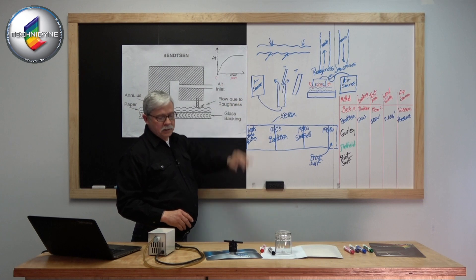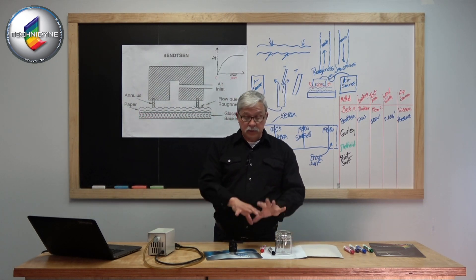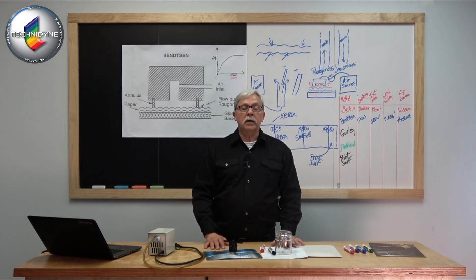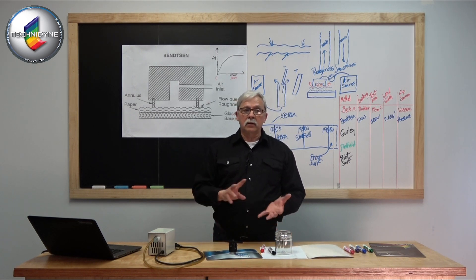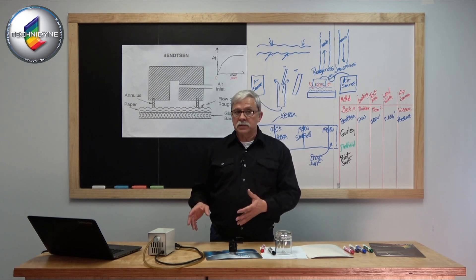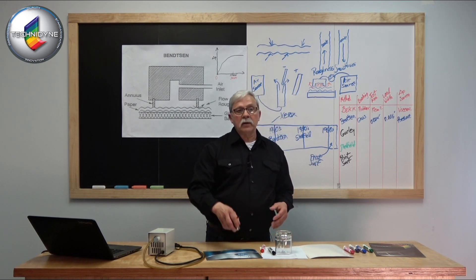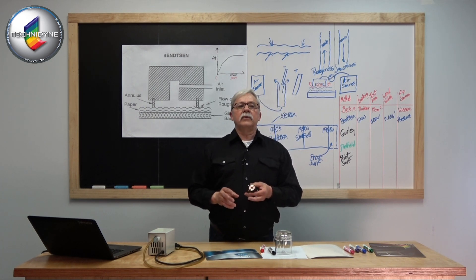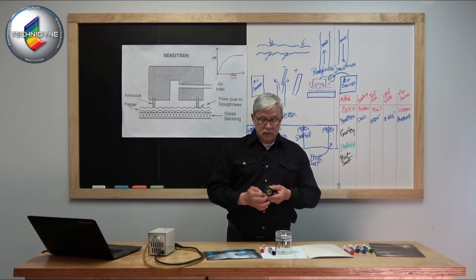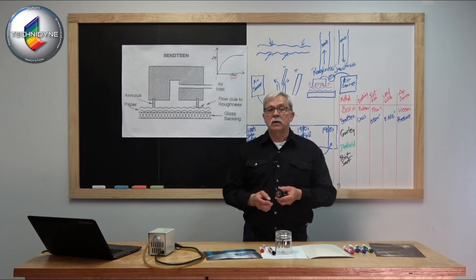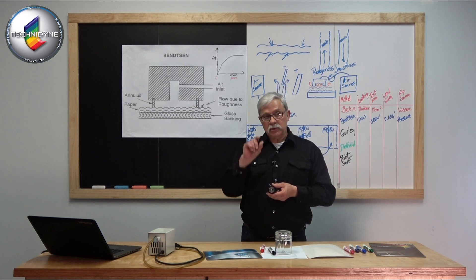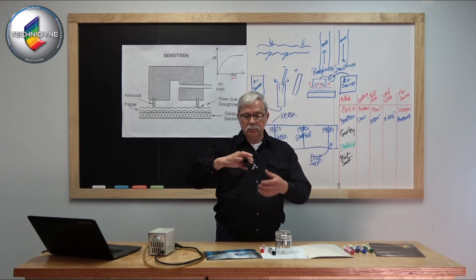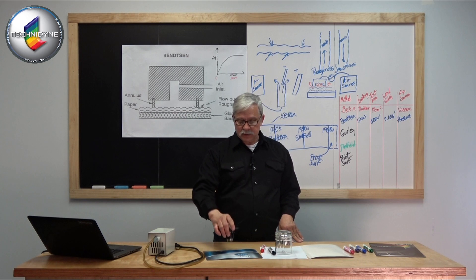We could build another instrument to duplicate what we've got here. In order to do that, however, we've got to maintain some of the components that are key to making one measurement system look and measure like the other. Certainly that very important component is the measurement head. The measurement head has to have the same circumference, the annular ring has to be the same dimension, the same width, and the overall mass of the mechanism has to be the same.